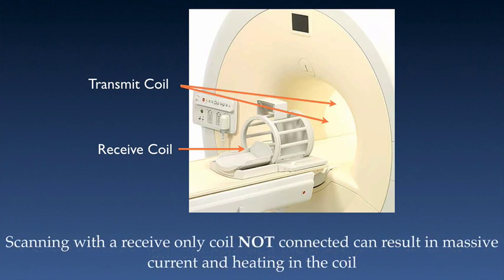It's very important to remember that you should never scan a receive-only coil that is not physically connected to the magnet. If the coil is not connected, the system does not know the coil is there, and therefore it won't be detuned during RF transmission. The least that could happen would be that you would damage or destroy the coil. The worst thing that can happen is that it would catch fire. So it is important to always scan with these coils plugged in, or remove them from the magnet if you're not going to be using them.